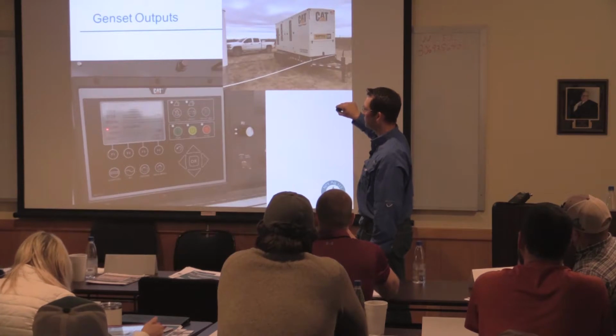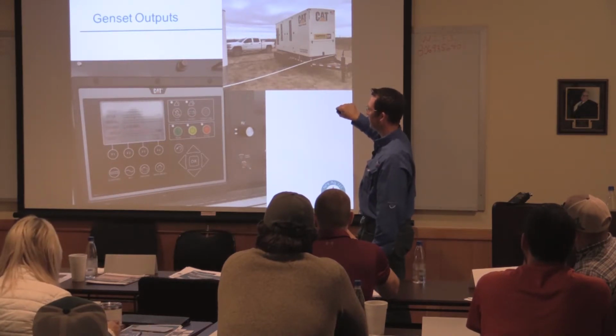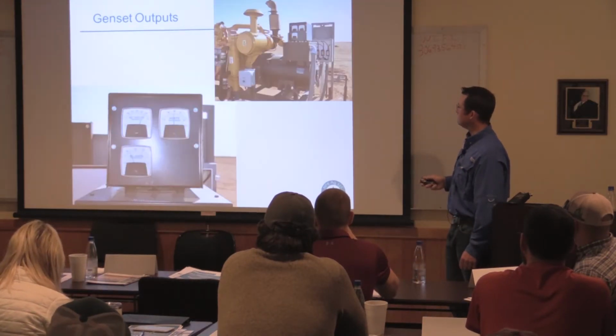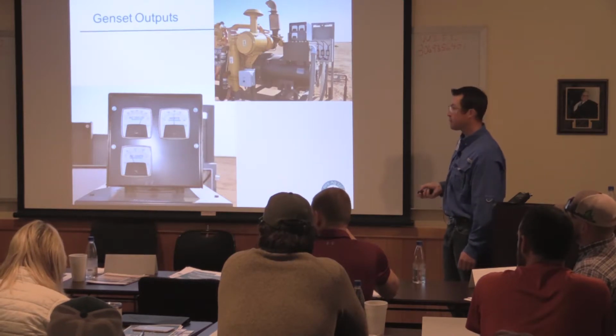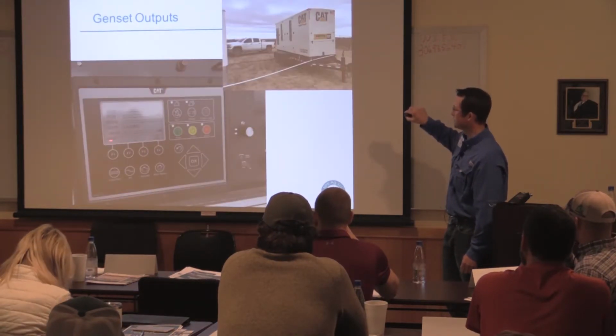This particular case is an old 400 horse motor currently being driven through a drive off of this, so it's got a bit of feedback, and you're at 0.93 on the power factor in the lagging position. It's producing 164 kilowatts.